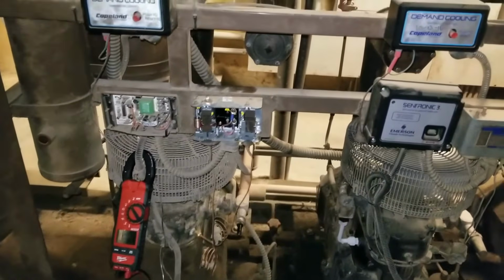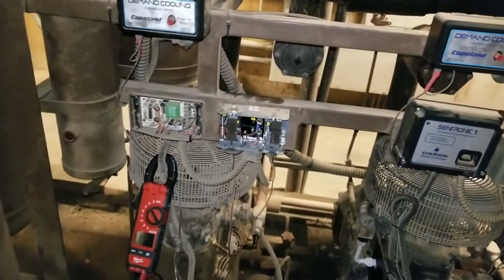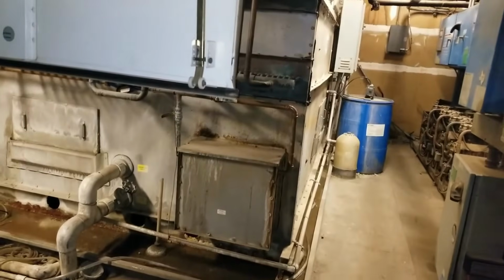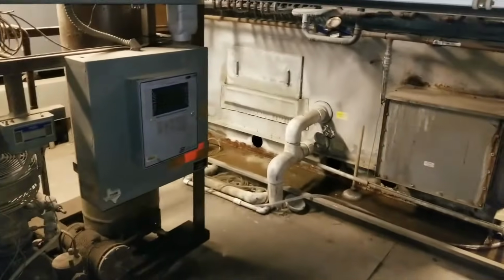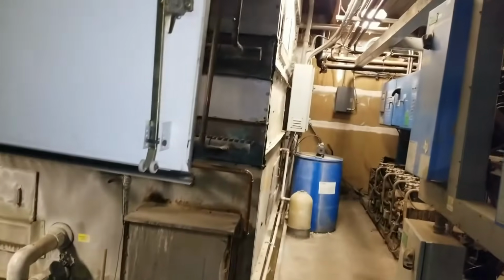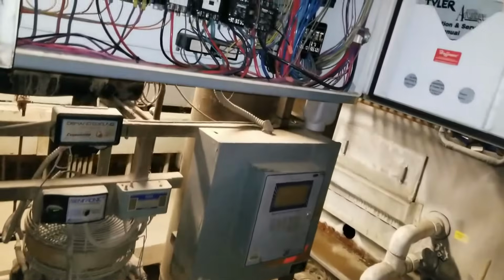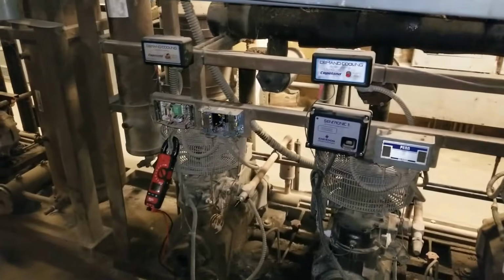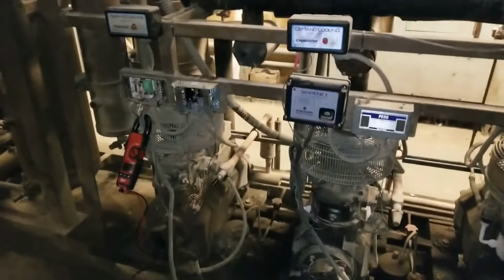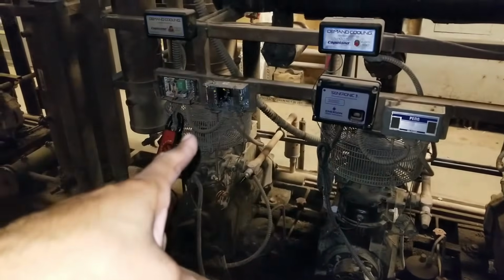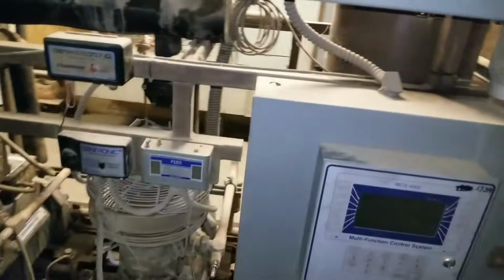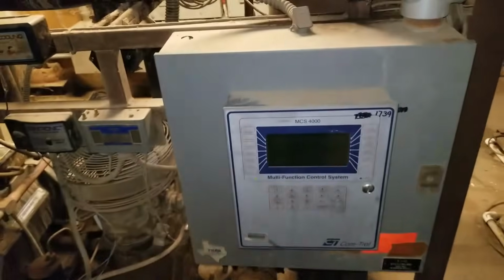So you kind of have to go over what the PT chart says in order to keep these things online. Yeah, you've got water cooling towers to cool down the condenser and the refrigerant, but sometimes that's not enough, especially on high humidity days. This thing's going to run 100% and the head pressure will still be up there. So that's why we adjust these up a little bit higher than what the PT chart calls for. So that's all done. Now it's cycling on and off like it should. And we're going to check out the controller now.